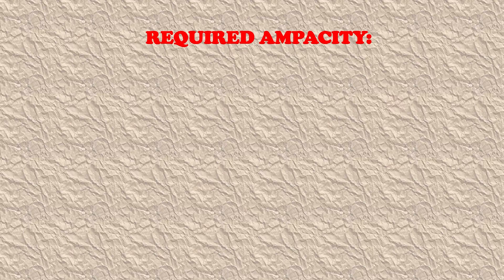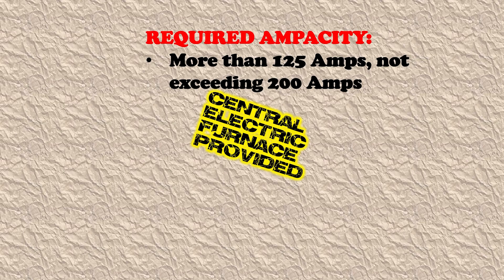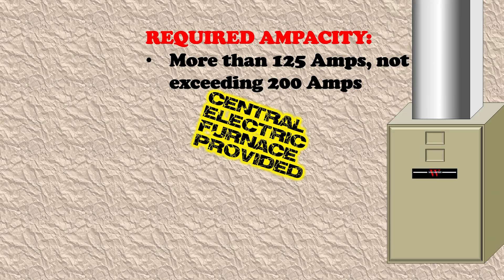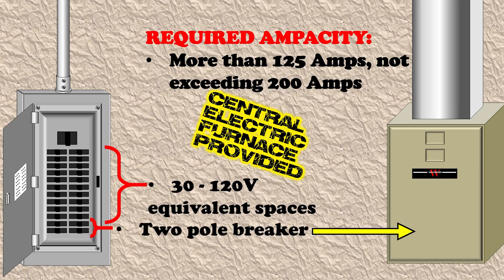In our next example, we're now more than 125 amps but not exceeding 200 amps inclusive, and a central electric furnace is provided. Because our central electric furnace is provided, we are again only required to have 30 of those 120-volt equivalent single pole spaces. The idea being that this furnace only takes up two of those panel spaces in the breaker.